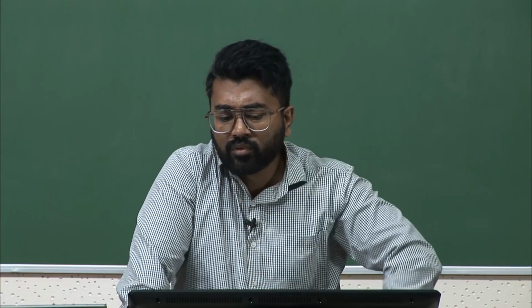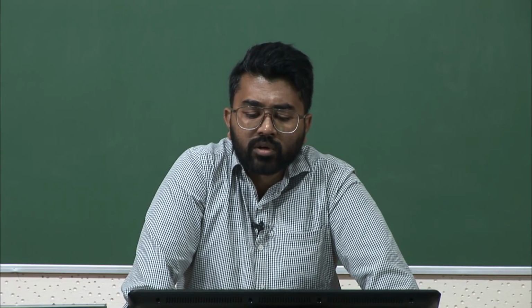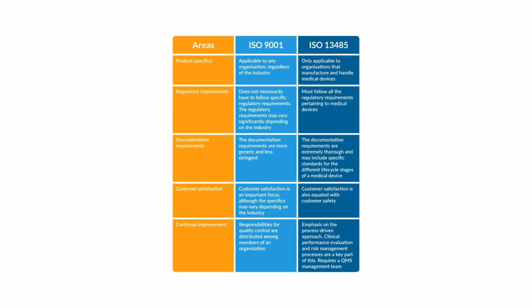ISO 13485 must follow all the regulatory requirements pertaining to medical devices. This is a must-follow for all medical devices. As far as documentation is concerned, the requirements are more generic and less stringent for 9001. For 13485, the documentation requirements are extremely thorough and may include specific standards for the different life cycle stages of the medical devices. Many of the medical device categories are clearly laid out here as per the classes.